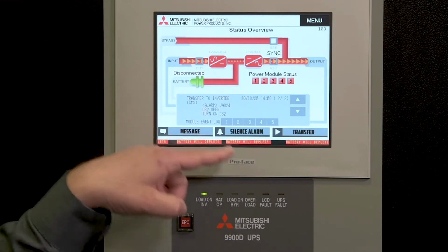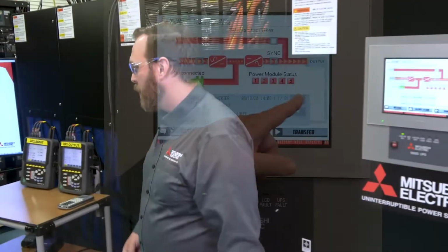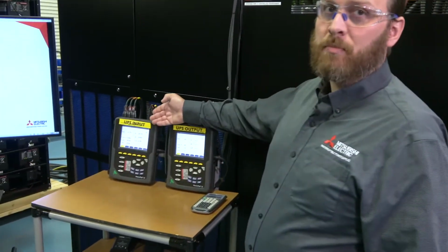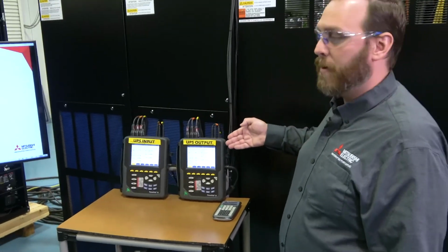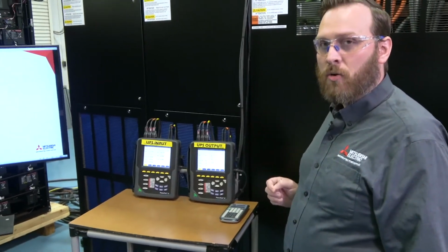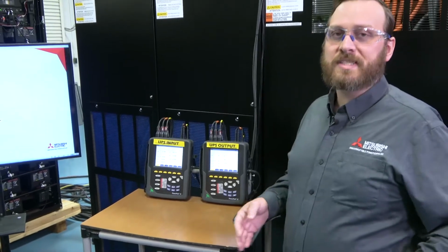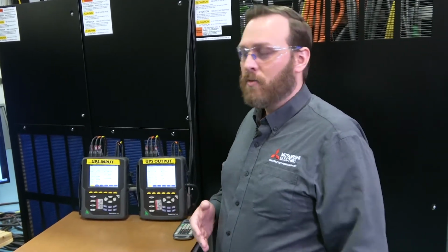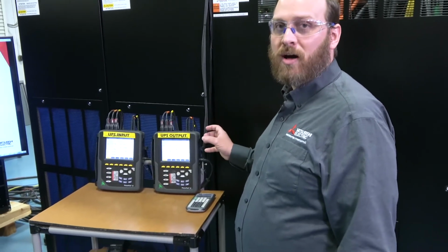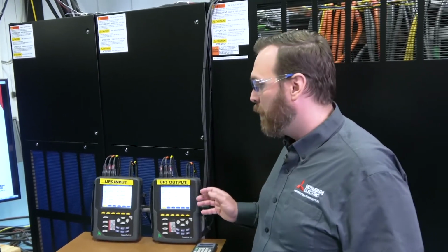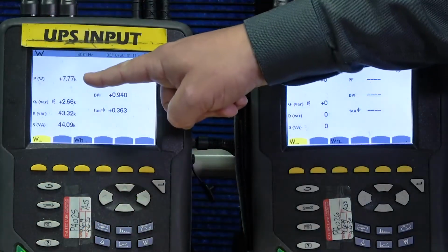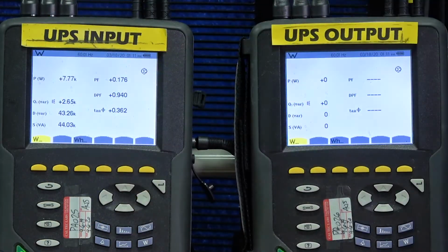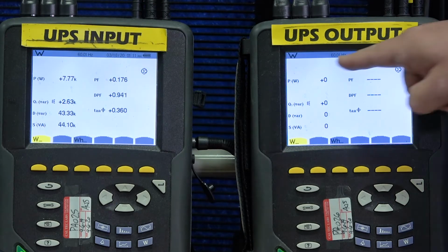So from here, we're going to take a step over here to our AEMC power meters for demonstrating the UPS input power versus UPS output power. One thing nice to show at 0% load is the overall system parasitic losses without any load on the UPS. So showing you how much power is lost just from the UPS sitting idle. Currently, on our input, we have 7.77 kilowatts of total loss to our UPS with no load on the output.